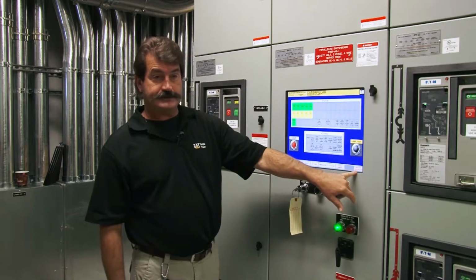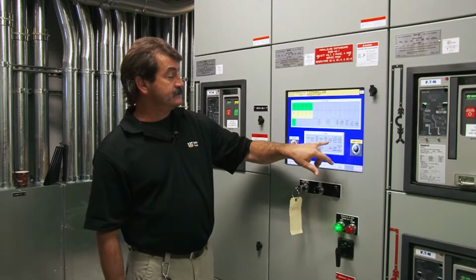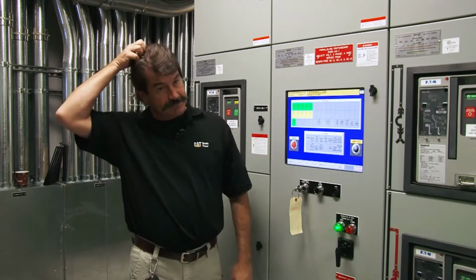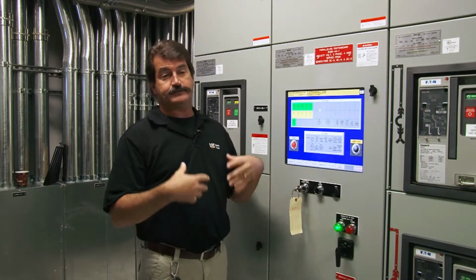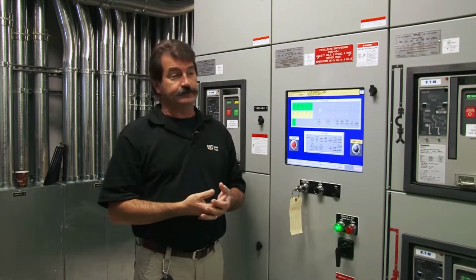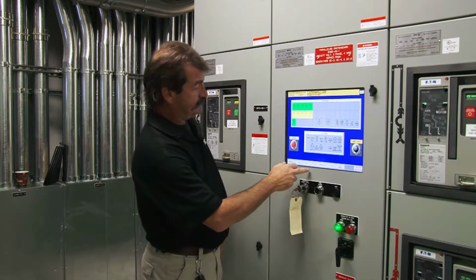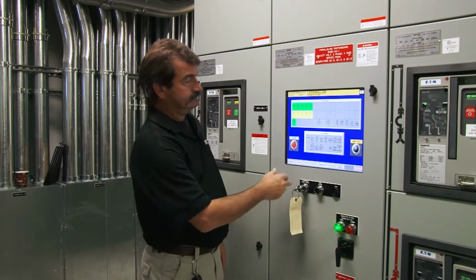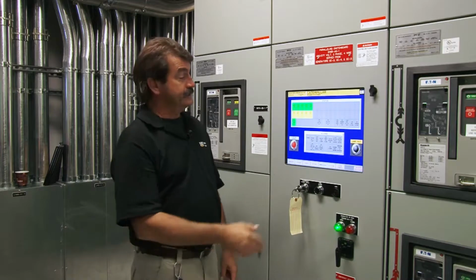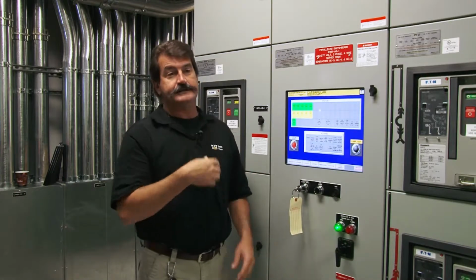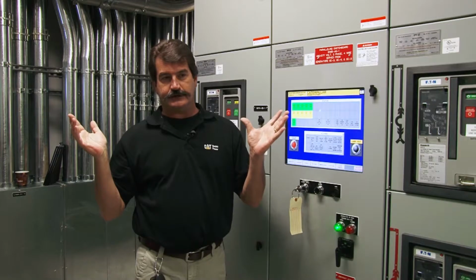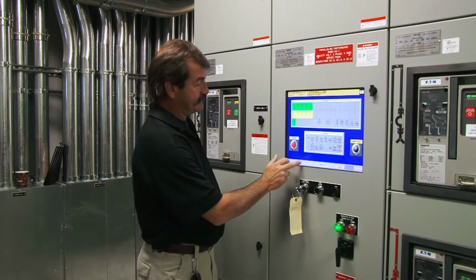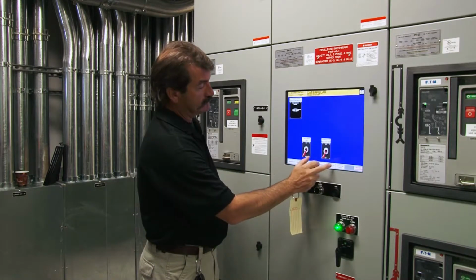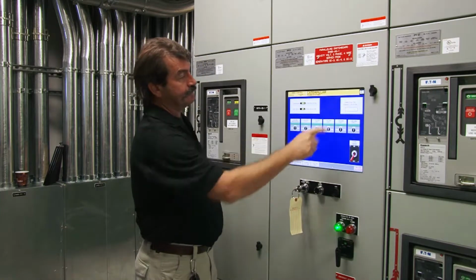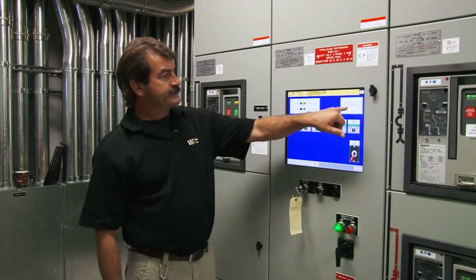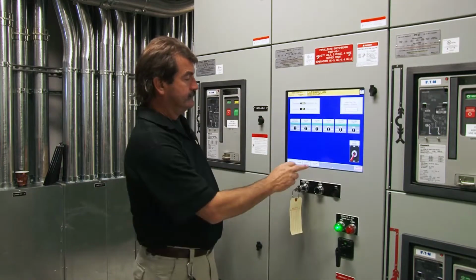Master shutdown, that's that right there. Bus under frequency. If for whatever reason the generator bus, whenever they're on, falls to less than, I believe it's 58 hertz, then you'll get a bus under frequency. It's going to open up every one of your distribution breakers if that ever happens. Let's look at that right quick. Control, load shed control, under frequency trip, okay? Set for 55 hertz.